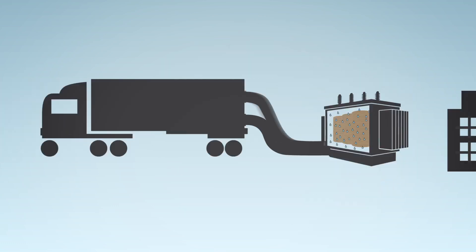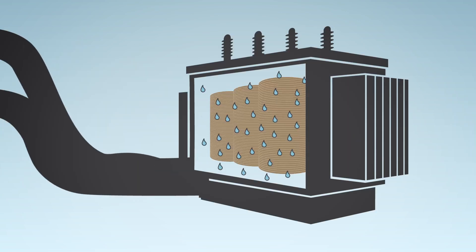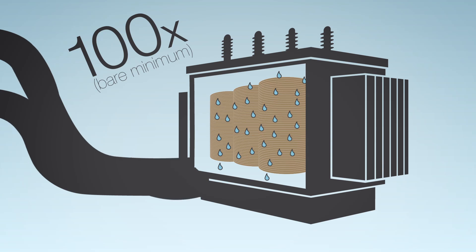So if testing shows high moisture levels in your transformer oil, you could bring in a rig and process the oil to remove the moisture. The problem with that is that the paper in your transformer holds at least 100 times more moisture than the oil itself.